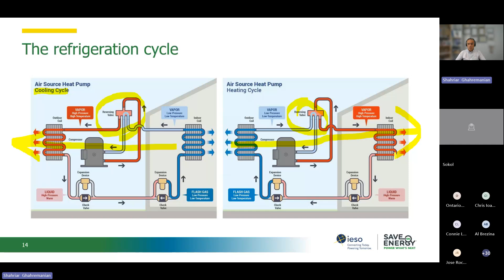Thanks to the reversing valve, this is the only extra component, I would say, that exists in a heat pump, which is different from an air conditioner. This reversing valve can switch the evaporator and condenser that we have in our heat pump system. So for the winter season, the reversing valve gets switched and basically takes the heat and dumps it inside our building. So the direction of the heat transfer will be from the outside toward the inside. And this is the only component added to our AC, I would say, for our air conditioning system to become a heat pump. That's a simplified version of it.